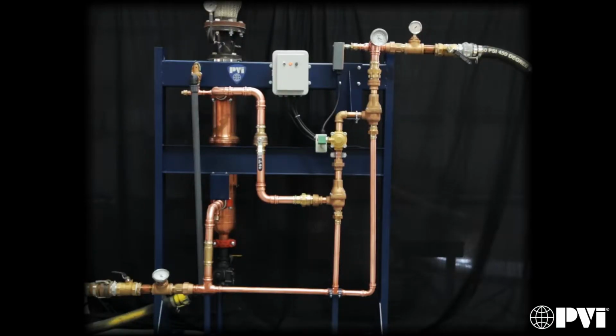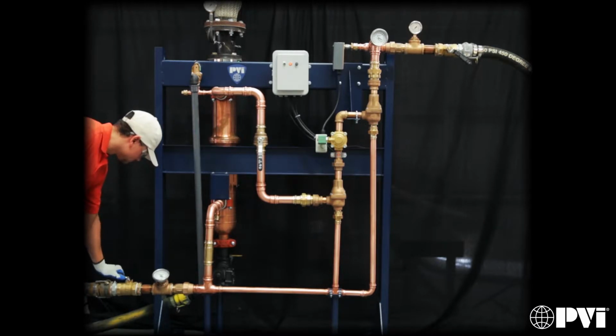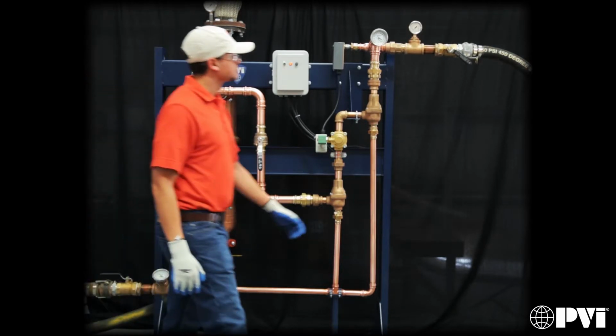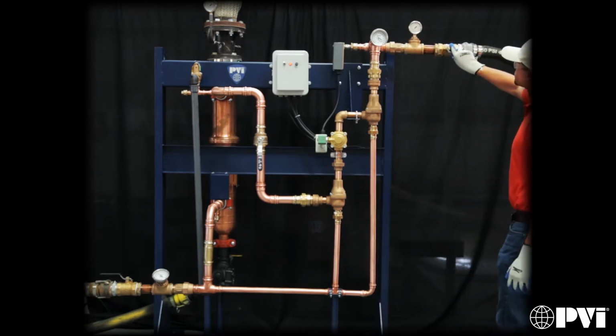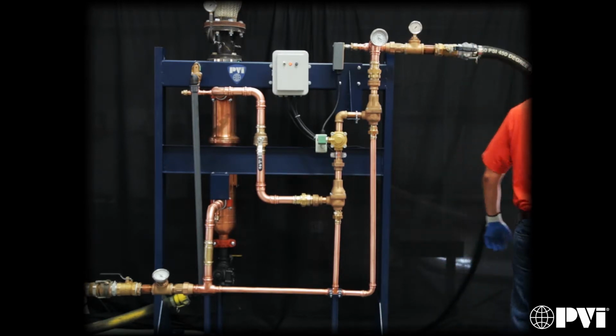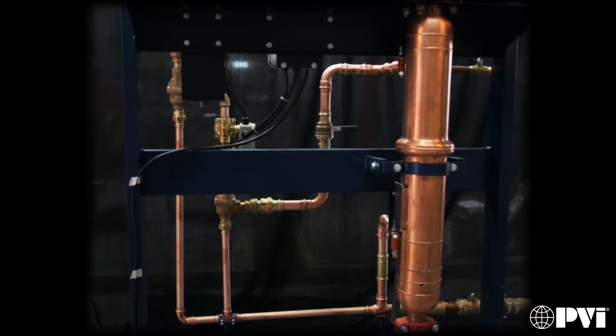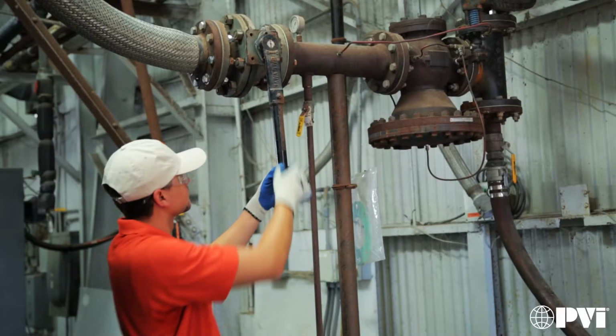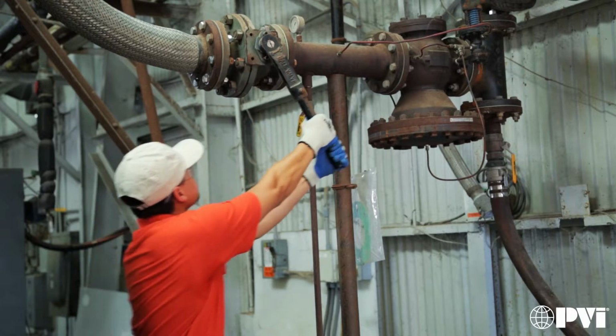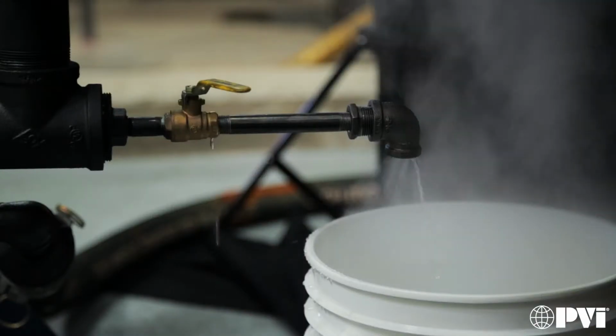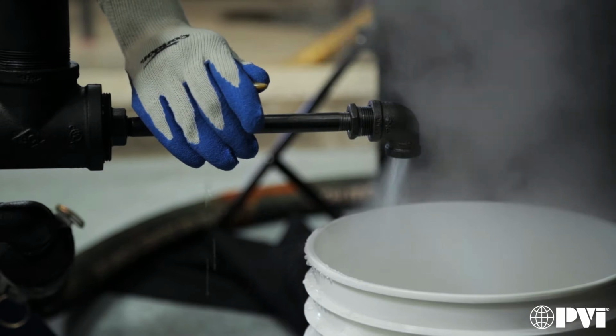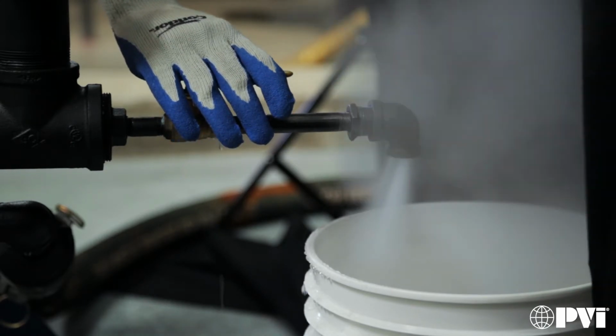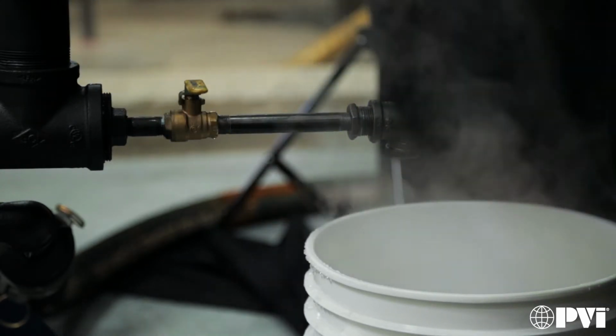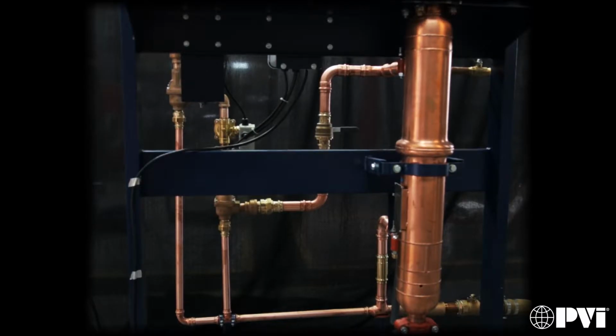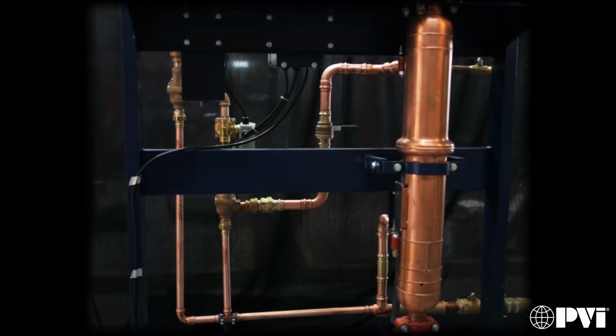When you have completed the air evacuation steps and the water side of the unit is fully operational, open the inlet water and water outlet valves to their full positions. Domestic water side setup is now complete. To prepare the steam side, slowly crack open the steam supply and allow condensate and air to discharge through the blowdown valves at the steam traps. When a plume of steam is discharged from the blowdown valves and no condensate appears, close the valve. With the blowdown valve closed, you may now fully open the steam supply valve to the unit.